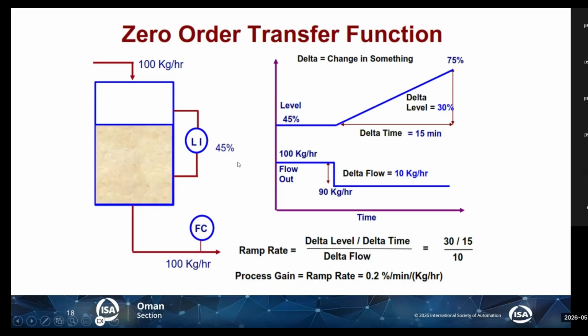So if I open, let us see here. So flow is 100%, as we said here. In this FC, it is 100%. I decreased the flow from 100 to 90. So what will happen? Because I'm closing the valve here and the same amount, 100, is coming in, you can see the level will start increasing without stopping. It will increase from 45 to 75 and to 100%, and then it will overfill.